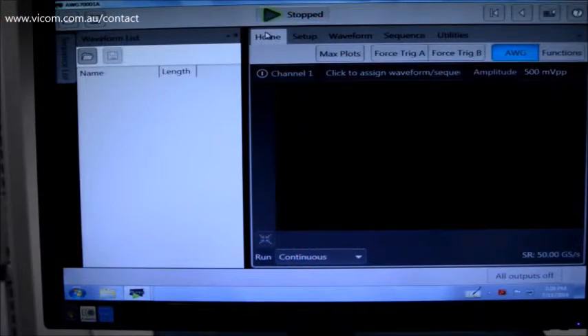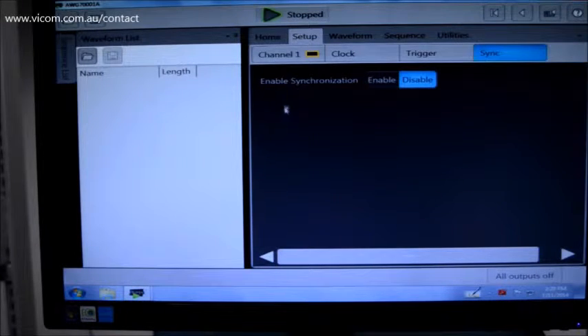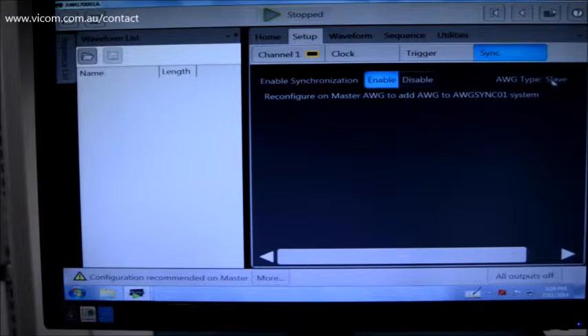So in order to use the sync hub, let's first look at a slave unit. So this is the UI for a slave, or for one of the AWGs, and for this particular case we're going to set it up as a slave. So we go under the setup menu, and you'll see that there's a sync selection, and then under the sync selection, it's very simple. I'm just going to enable it, and if nothing else is connected, it'll give you a prompt of either a master or a slave. I have this one already configured to be a slave. So basically that's all you have to do on your slave.